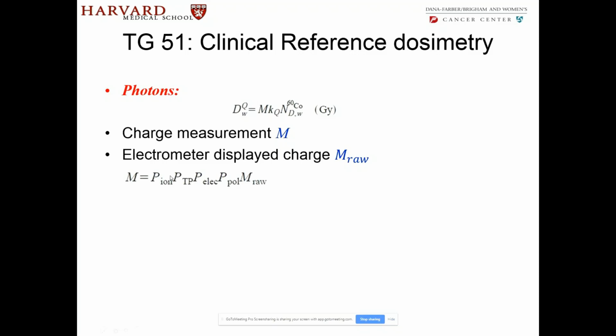You have the ion chamber correction, the ionization inefficiency correction. This is temperature and pressure. This is for the electrometer. This is the polarity issues that might arise during measurements. You take all those corrections, multiply M raw, and you have the final value of M.